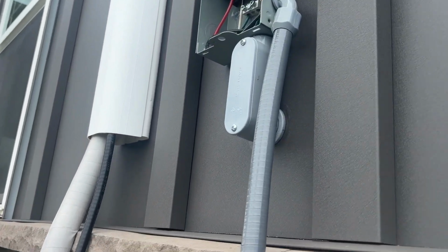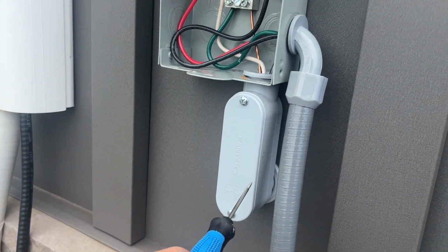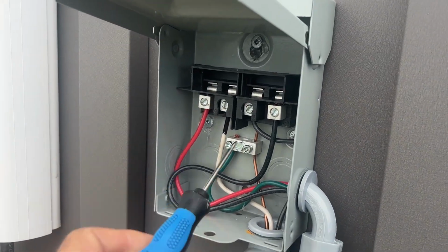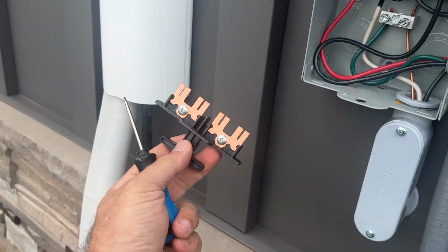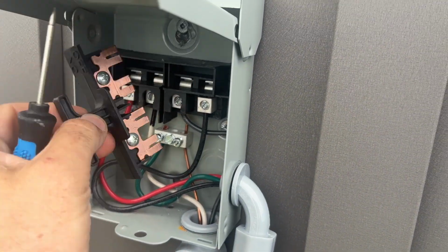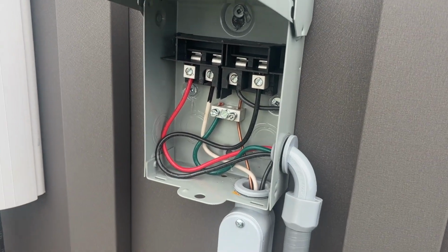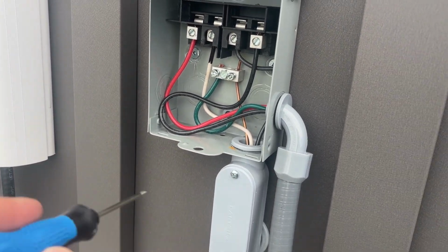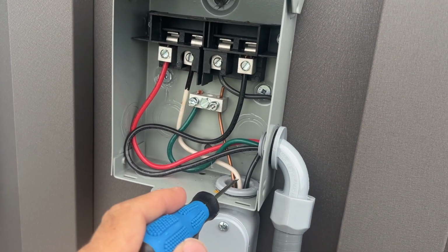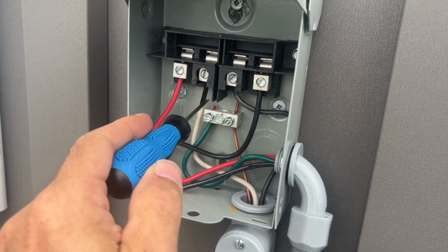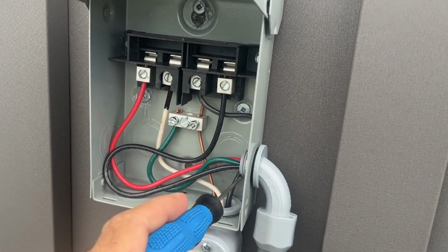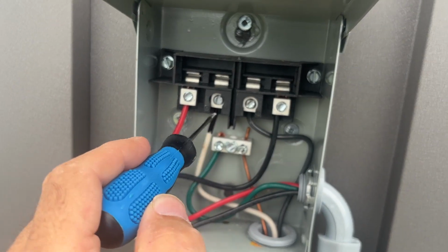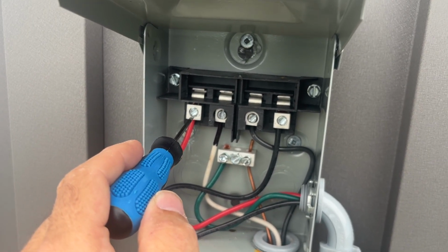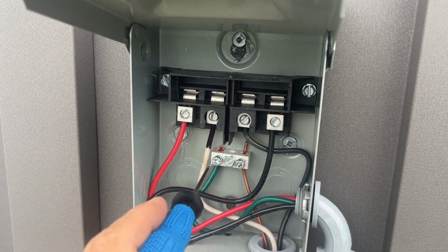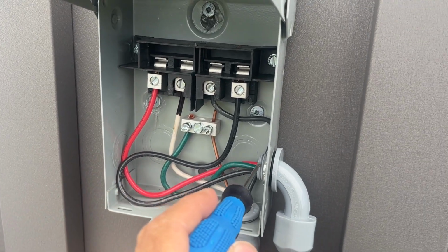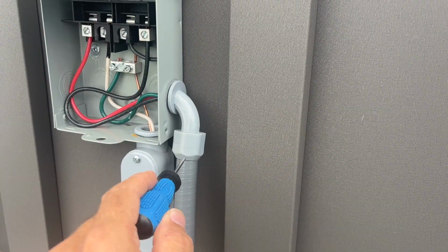Now, my 10-2 wire pokes out of the wall here in the elbow up to my AC disconnect. And that is basically this piece here. I'm either connected or flipping it out and disconnecting it, and that shuts power down to the entire unit. Now my 10-2 wire comes in here, and you can see I have this designated as a hot, and then my black here is coming up here. So my two inputs, and then the output is the red and the black here, and I of course have both my grounds.